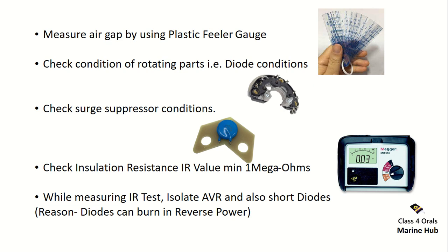Check the condition of the rotating parts — that is, the diodes condition — whether they are burnt or in a bad state. Also check the surge suppressor condition, shown in the photo as a blue-colored surge suppressor. Next, measure the insulation resistance — the minimum IR value is 1 mega ohm. Make sure while measuring the IR test, always isolate the AVR and also short the diodes, as reverse power could otherwise burn the diodes.